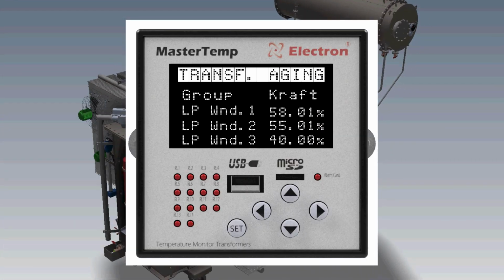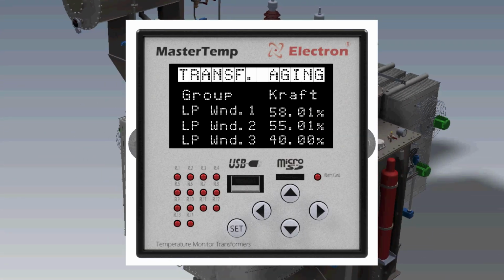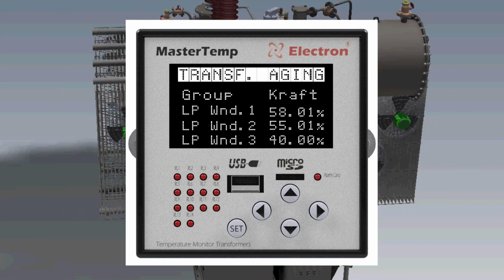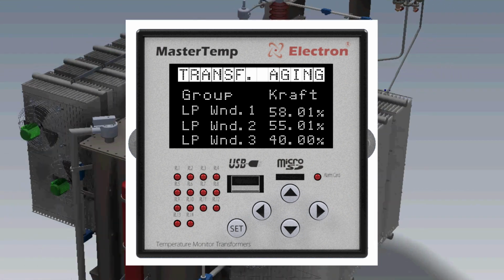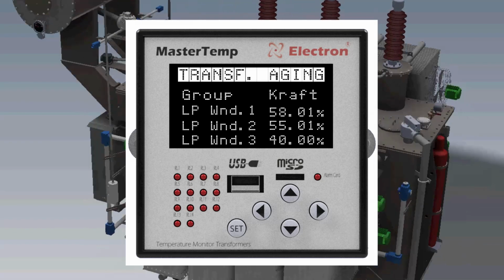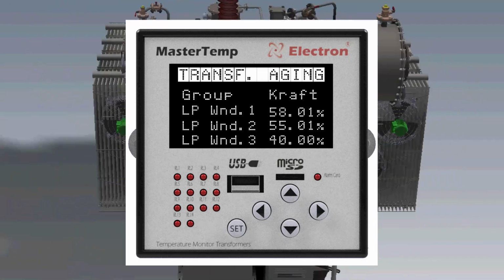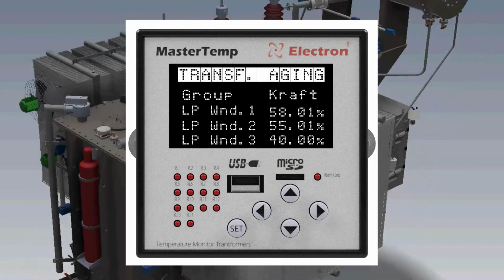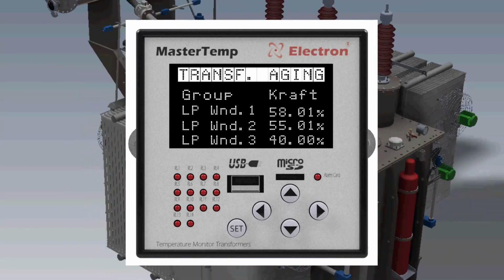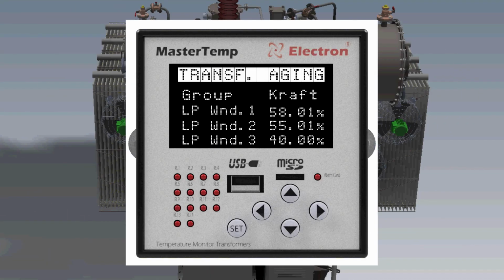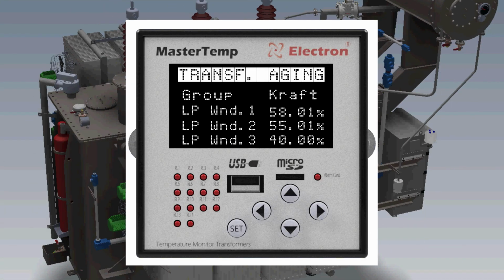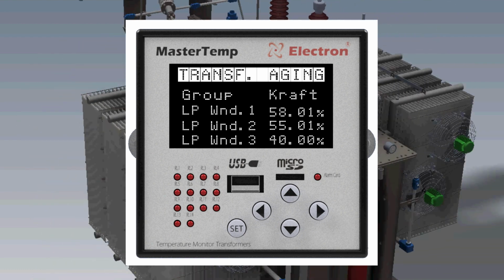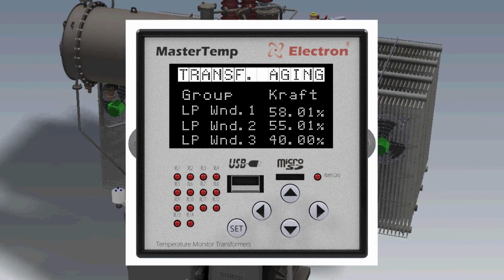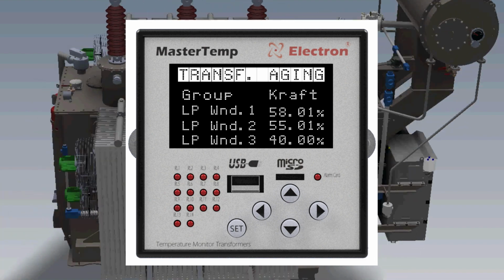It has been implemented in Mastertemp engineering algorithms that calculate the aging of the transformer, that is, the loss of life, and the remaining life of each winding, based on the equation of the Arrhenius reaction, which is the basic principle for thermal aging calculations. The result of the calculation is processed minute by minute, presenting the transformer's loss of life, and the transformer's remaining life. To achieve a precise result, choose the correct type of insulation.